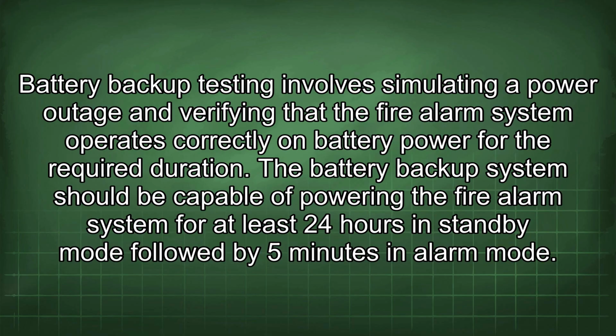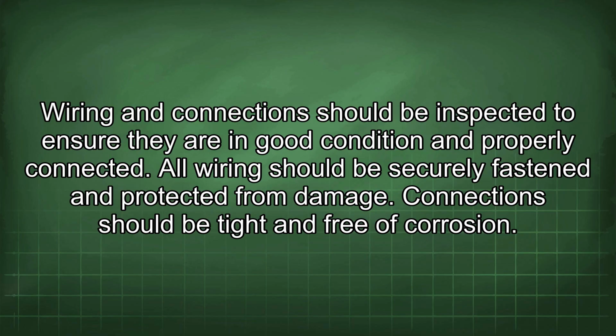Battery backup testing involves simulating a power outage and verifying that the fire alarm system operates correctly on battery power for the required duration. The battery backup system should be capable of powering the fire alarm system for at least 24 hours in standby mode followed by 5 minutes in alarm mode. Wiring and connections should be inspected to ensure they are in good condition and properly connected. All wiring should be securely fastened and protected from damage. Connections should be tight and free of corrosion.